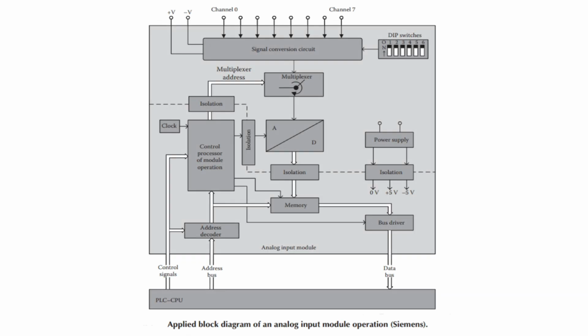The module's design ensures that analog and digital components are electrically isolated to protect the PLC's microprocessor and other sensitive electronic parts from potential damage, which can be caused by electric noise, surges or any fault. The microprocessor within the module manages the overall functionality and includes the operation of the multiplexer, analog to digital converter and the memory.